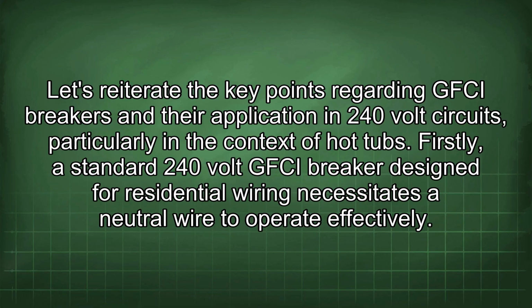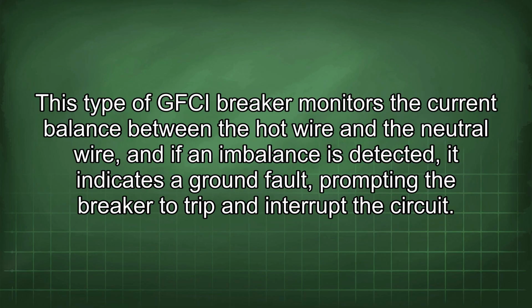Let's reiterate the key points regarding GFCI breakers and their application in 240-volt circuits, particularly in the context of hot tubs. Firstly, a standard 240-volt GFCI breaker designed for residential wiring necessitates a neutral wire to operate effectively. This type of GFCI breaker monitors the current balance between the hot wire and the neutral wire, and if an imbalance is detected, it indicates a ground fault, prompting the breaker to trip and interrupt the circuit.